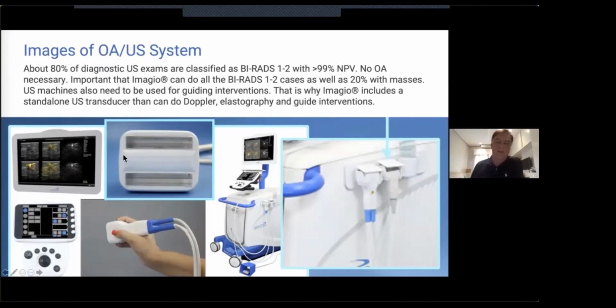The ultrasound transducer is in the center. And there are 2 quartz laser windows on either side, and both wavelengths are fired out of both. The wavelengths cause a thermoelastic expansion when they're absorbed in blood vessels in the breast, and then the ultrasound detects the pressure waves coming back. This is a side view. The larger cable is the one that carries the fiber optics, the smaller carries the ultrasound information.